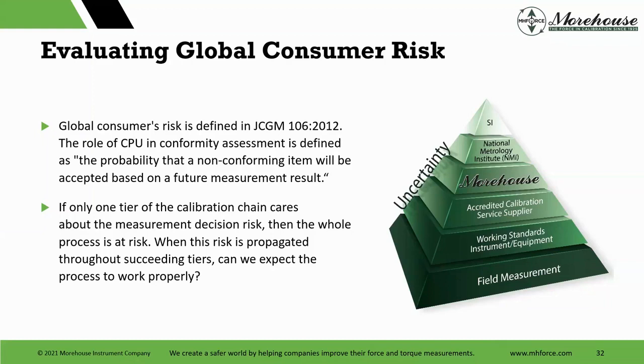So if we send a device to an NMI and they make a mistake, it's going to go down. That's going to impact us. We do cals for you. That's going to impact you the whole way down. So wherever that mistake occurs, it goes the whole way down. So if only one tier of the calibration chain cares about the measurement decision risk, then the whole process is at risk. When this risk is propagated throughout succeeding tiers, can we expect the process to work properly? We can't. Eventually, it's going to fail.